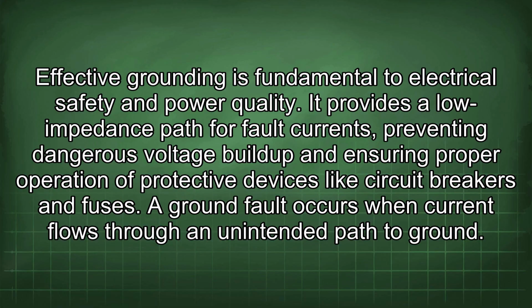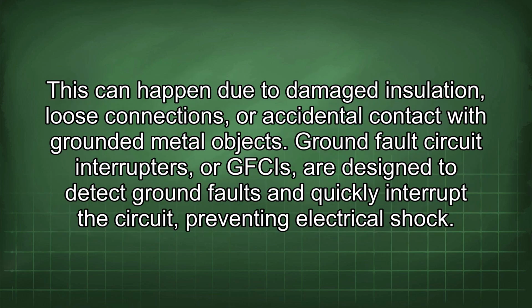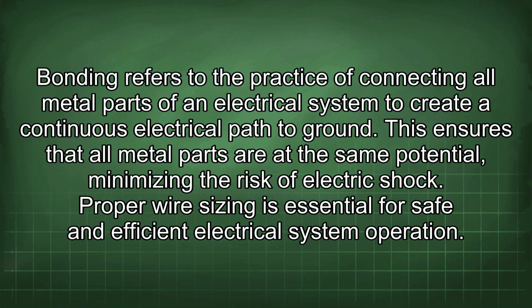A ground fault occurs when current flows through an unintended path to ground. This can happen due to damaged insulation, loose connections, or accidental contact with grounded metal objects. Ground fault circuit interrupters, or GFCIs, are designed to detect ground faults and quickly interrupt the circuit, preventing electrical shock. Bonding refers to the practice of connecting all metal parts of an electrical system to create a continuous electrical path to ground. This ensures that all metal parts are at the same potential, minimizing the risk of electric shock.